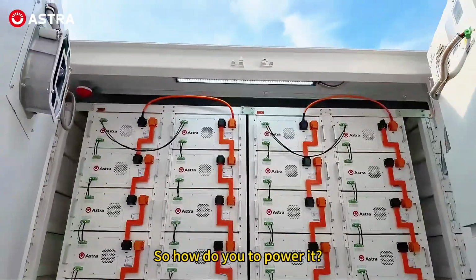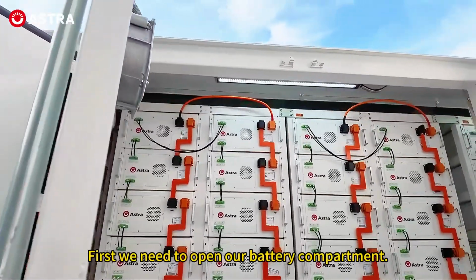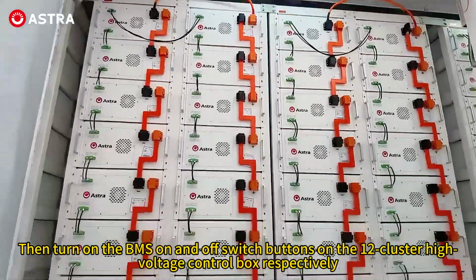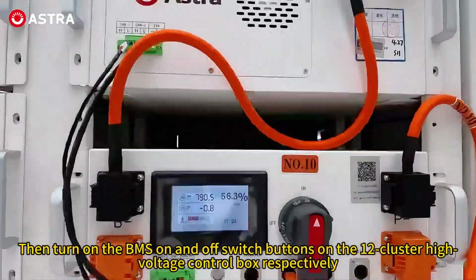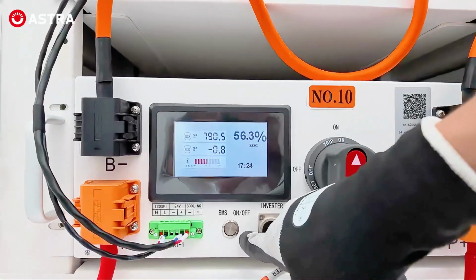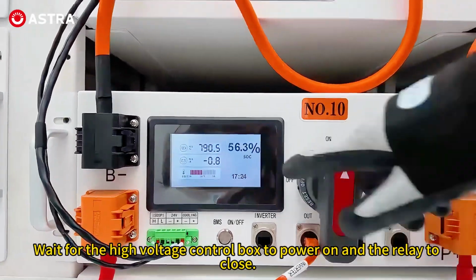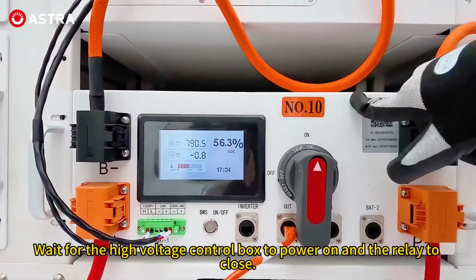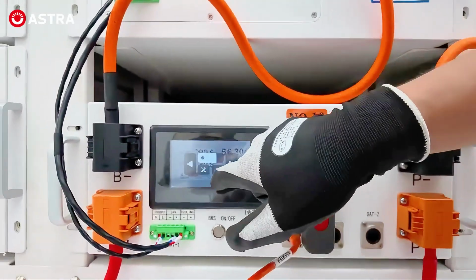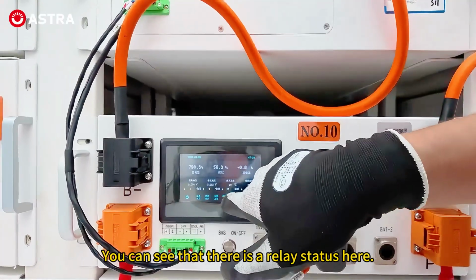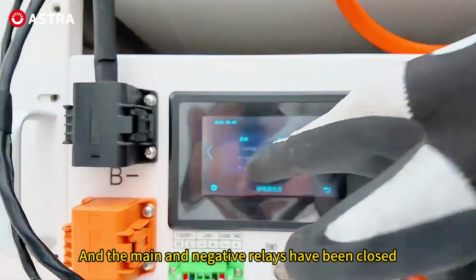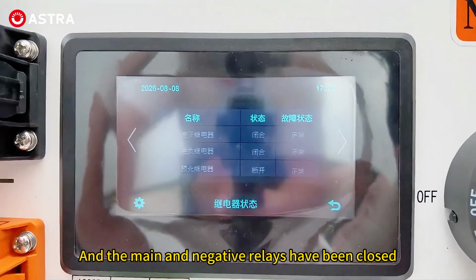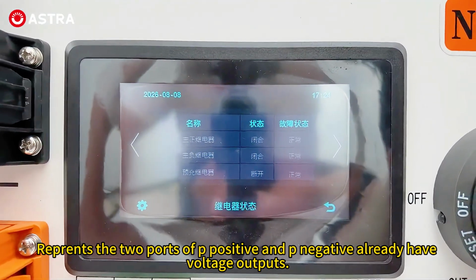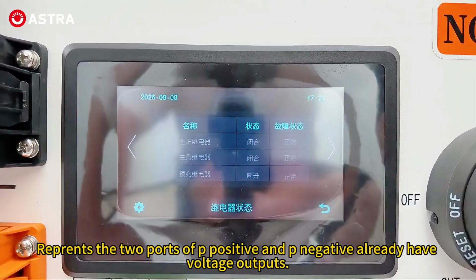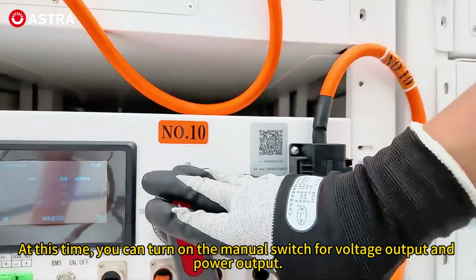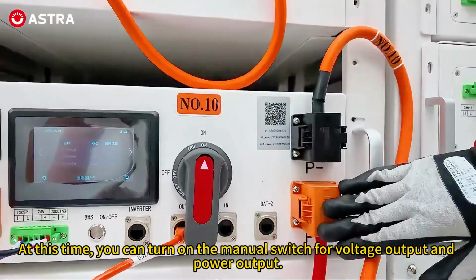So how do you power it? First we need to open our battery compartment. Then turn on the BMS on and off switch buttons on the 12 cluster high voltage control box respectively. Wait for the high voltage control box to power on and the relay to close. You can see that there is a relay status here. You can see the main positive relay and the main negative relay have been closed. The two ports of P positive and P negative already have voltage outputs. At this time, you can turn on the manual switch for voltage output and power output.